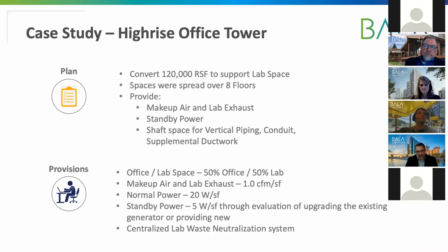And as far as comparing to the metrics, as I mentioned, we went with the 1 CFM per square foot average. Our normal power actually was at 20 watts. So again, the numbers I mentioned earlier were averages. So you can see here we're slightly above the average of 15 watts per square foot. Standby power, we're right on that 5 watt per square foot metric.